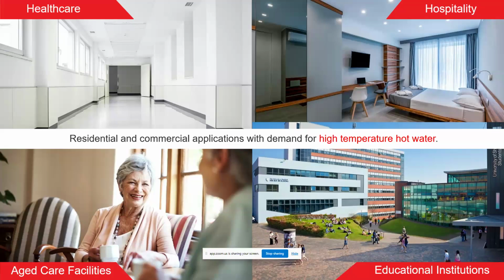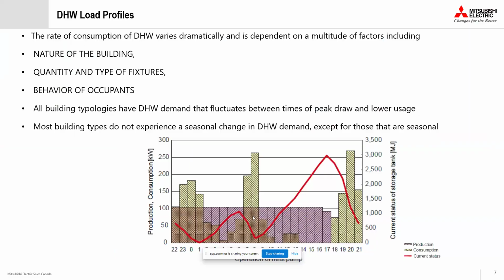Whether you are a single home, hospital, hotel, or healthcare, everywhere there is a need for hot water. So what does the hot water profile or hot water need look like? The rate of consumption for domestic hot water varies dramatically. It's not like heating and cooling, where you have a worst scenario at a peak either in the summer or winter. It all depends on a multitude of factors, including the nature of the building. So a residential building has a different consumption. If you have a hotel, it will have different consumption. So maybe in the same 10-story building, because of the nature of the building, you will have different consumption or different requirements for the hot water.